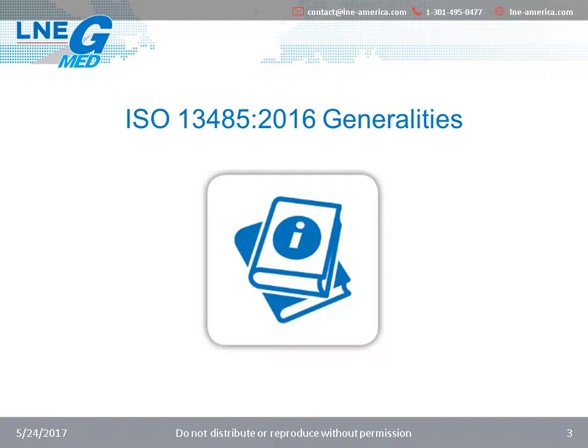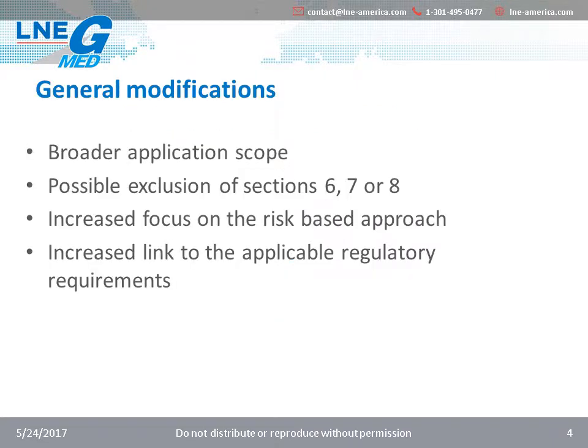Let's get started with a few generalities about the changes in ISO 13485:2016. The standard is now aiming to reach a broader audience in the medical device actors, from legal manufacturers to subcontractors, to consultants, to distributors, some of them being suppliers of the others.